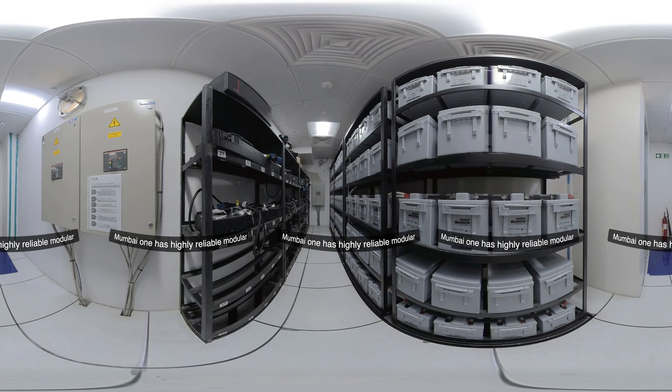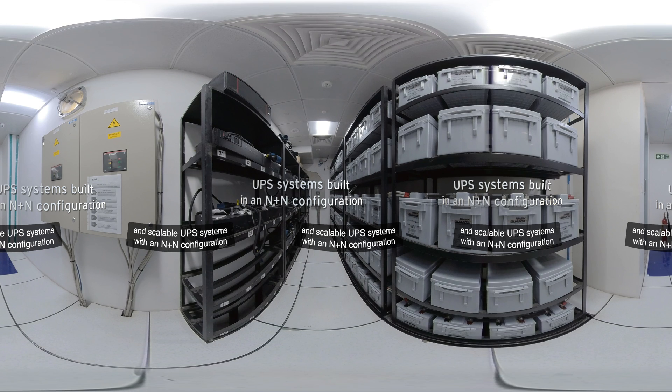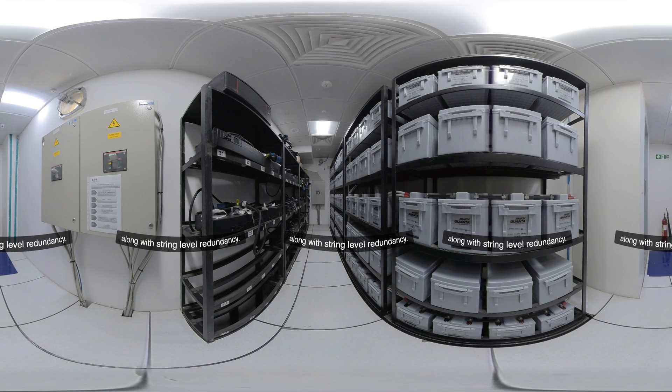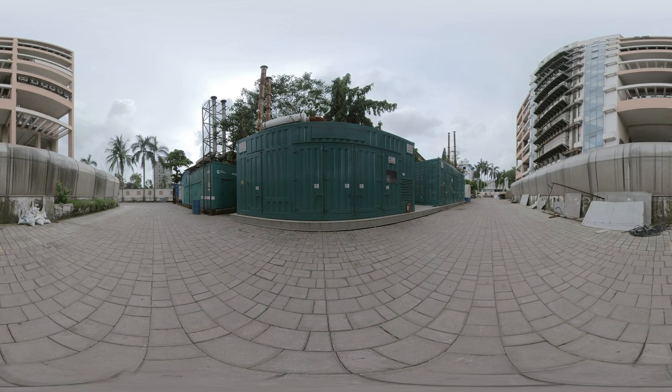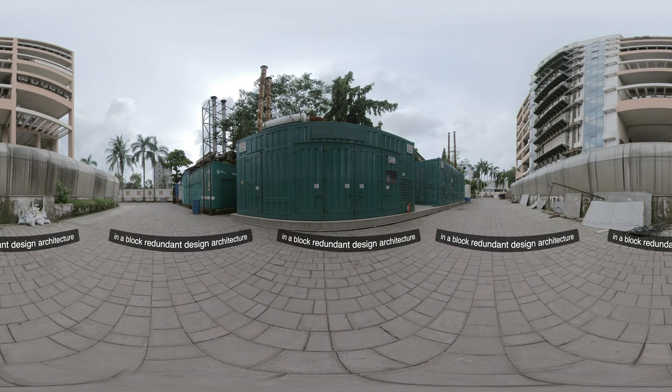Mumbai One has highly reliable modular and scalable UPS systems with an N plus N configuration, backed by batteries located in separate rooms along with string level redundancy. Generators are built in a block redundant design architecture with system level redundancy of N plus two.